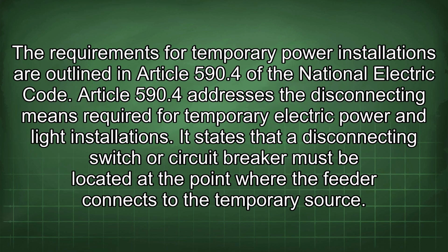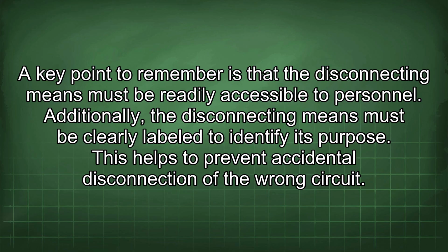The requirements for temporary power installations are outlined in Article 590.4 of the National Electric Code. Article 590.4 addresses the disconnecting means required for temporary electric power and light installations. It states that a disconnecting switch or circuit breaker must be located at the point where the feeder connects to the temporary source. A key point to remember is that the disconnecting means must be readily accessible to personnel.